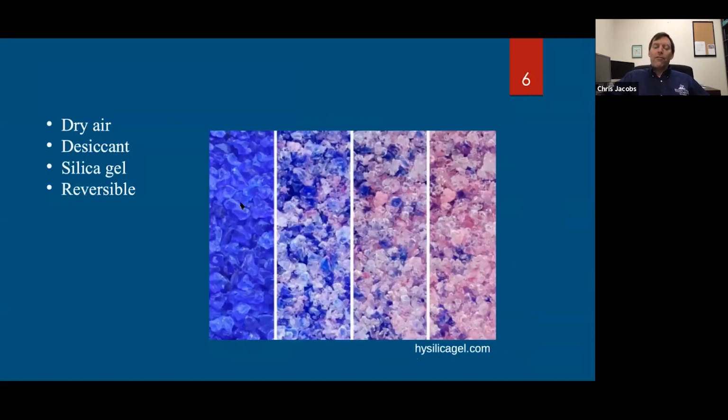These colors are reference colors. These can absorb a significant amount of moisture from the air. These are not designed to go from blue to pink during one test. If the air content is fairly dry, then you will not be pulling that much moisture out of it. And the air down there was fairly dry.